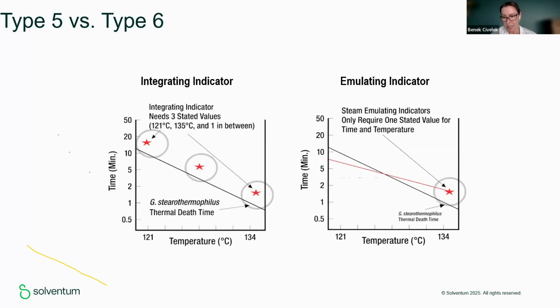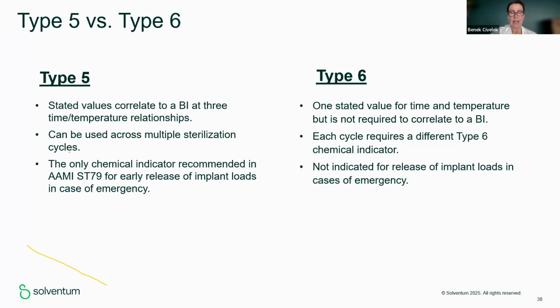This chart also shows us that there is a difference between an integrated indicator type 5 and a type 6 emulating indicator. Testing, because we always talk about these three stated values correlating with a BI, but here the emulating indicator doesn't have a correlation with a BI and is only tested at one time and temperature relation. Another comparison concerns the stated values: type 5 has three time and temperature relationships, but type 6 has one.